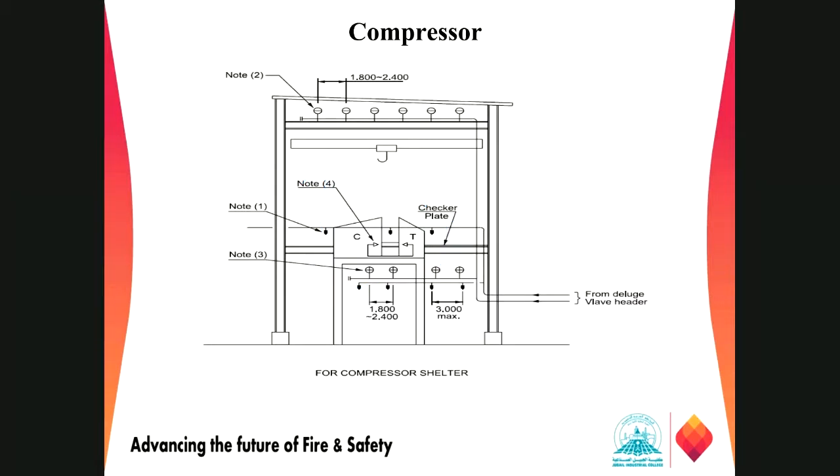At the ceiling, we need a sprinkler system, right? That sprinkler system is as per NFPA 13. And at the bottom, we have heat detectors. We detect the fire, and then we have nozzle locations. They can be water spray nozzles with different arrangements.